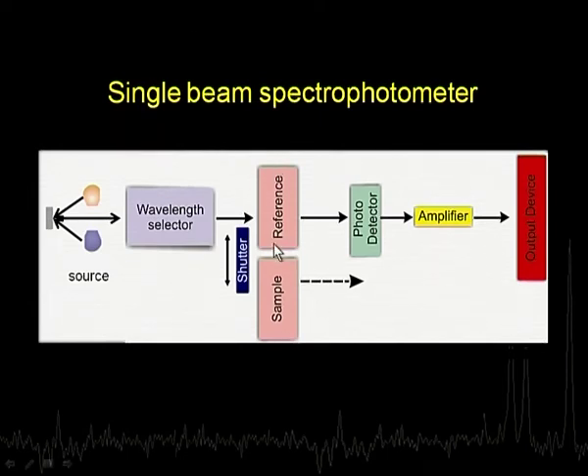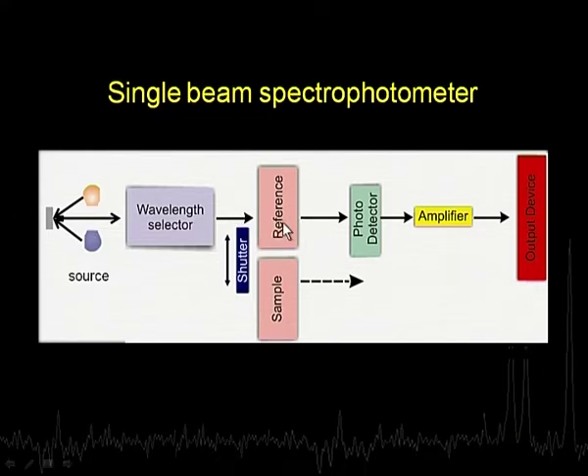So what we do is start with taking the reference first. The reference is the same cuvette which contains everything but the compound we want to measure - basically just the solvent system. We make the radiation pass through this and measure how much is absorbed. This is done over the whole range. We start from about 200 nanometers and go to 300, 700, or whatever the range may be. For every wavelength, the measurement is made and stored in the computer memory.